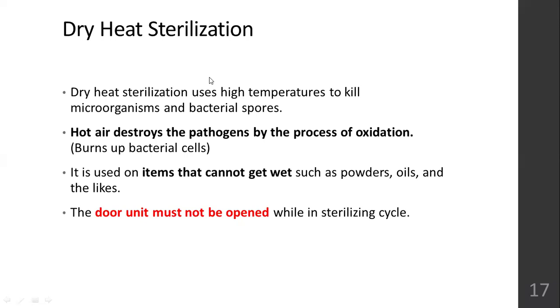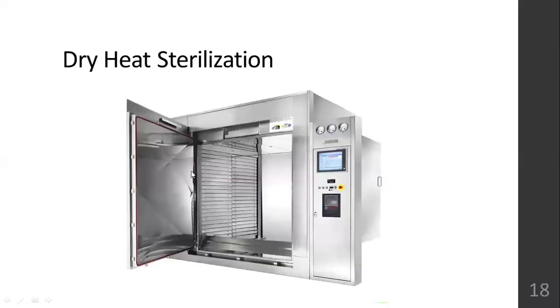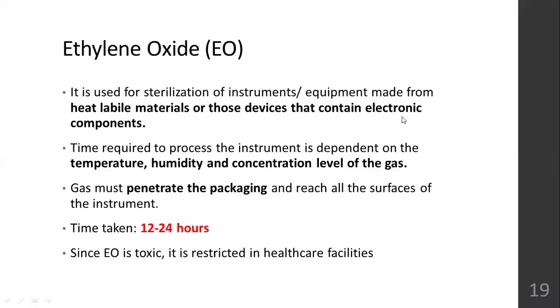And the door of the unit should not be opened when the sterilization cycle is ongoing, because the outside air is cold and the inside air of a hot air oven is very hot. If you immediately open the door soon after the cycle or in between the cycle, all the glass items can break because of the sudden shift in temperature. Okay. You cannot use it for things that are liquids and all. So this is how a hot air oven looks like.